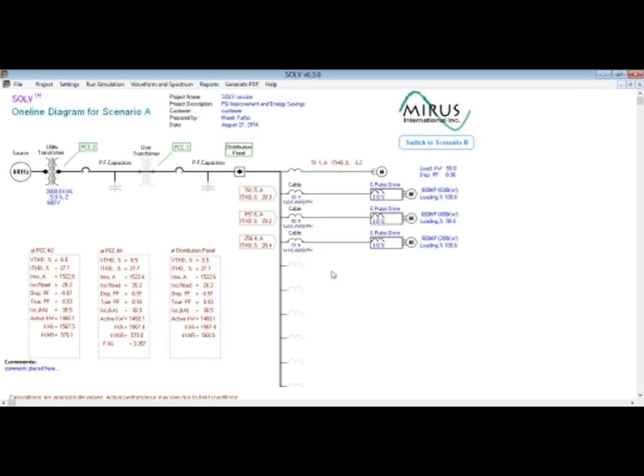Okay, a few more questions. Do Mirus filters include capacitors? These create problems with generators. Does Mirus include a contactor for opening the filter when on standby power generator units? This is a perfect question. I love these questions because yes, Mirus filters include capacitors, and no, we don't have problems with generators because our capacitor bank is very small compared to any other filter on the market. It's actually 1/3 of the standard passive filter that's on the market.